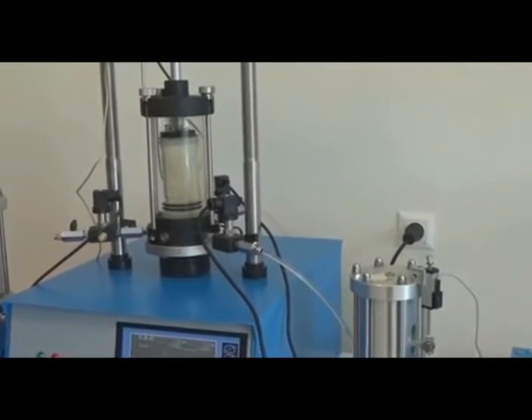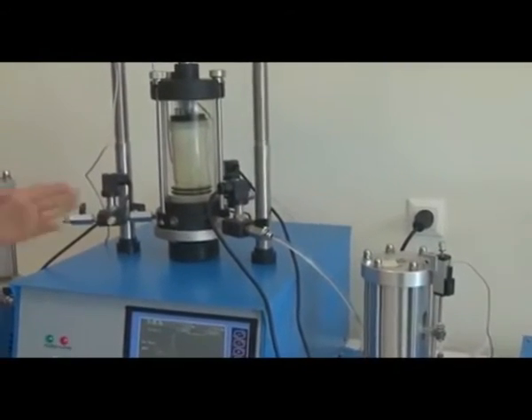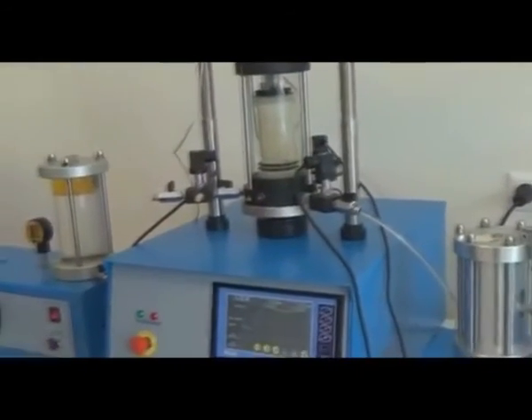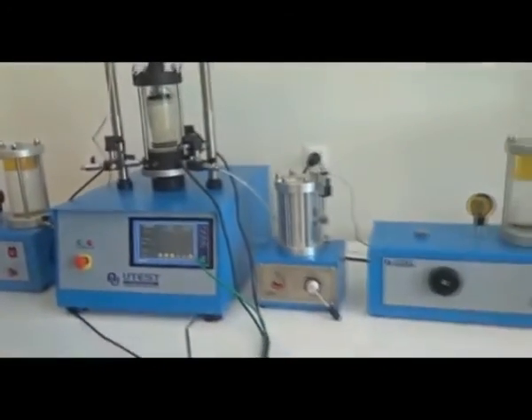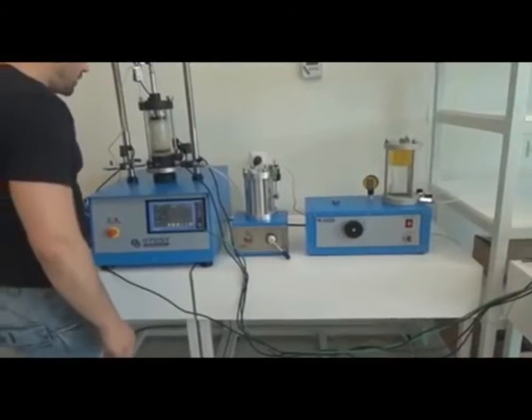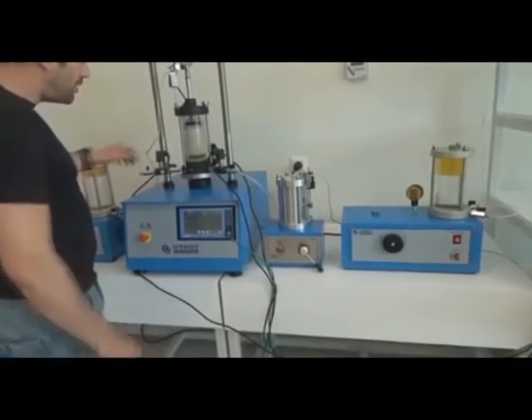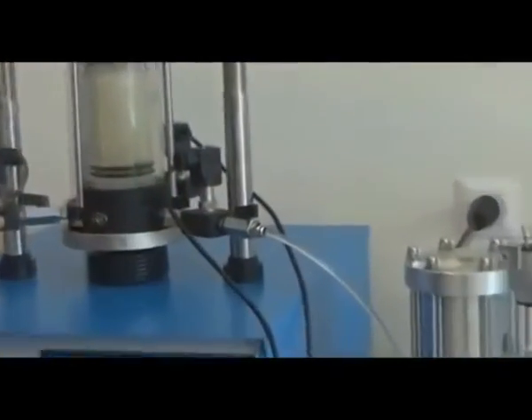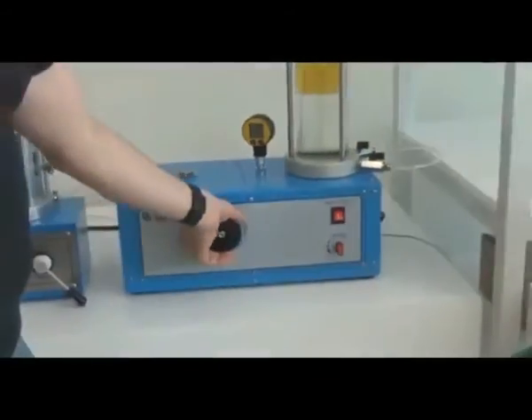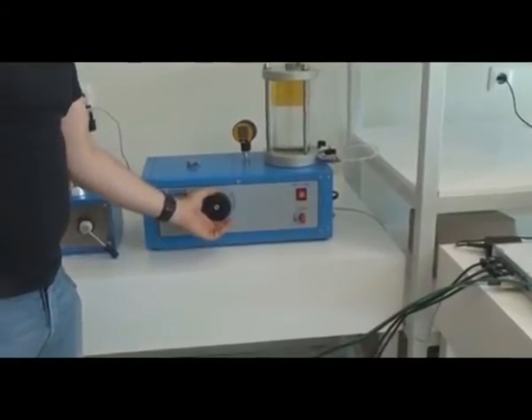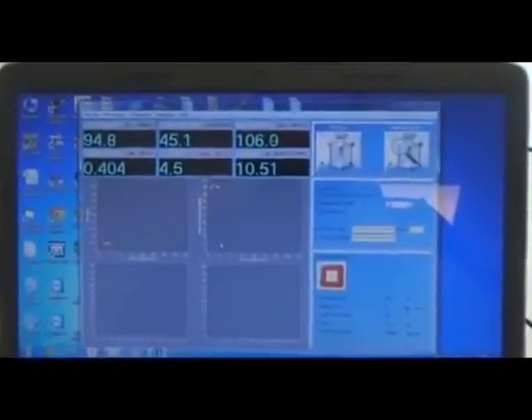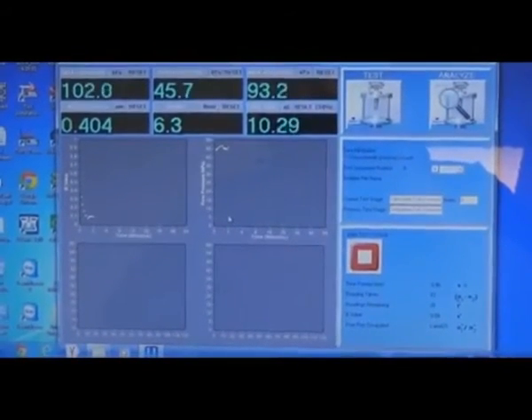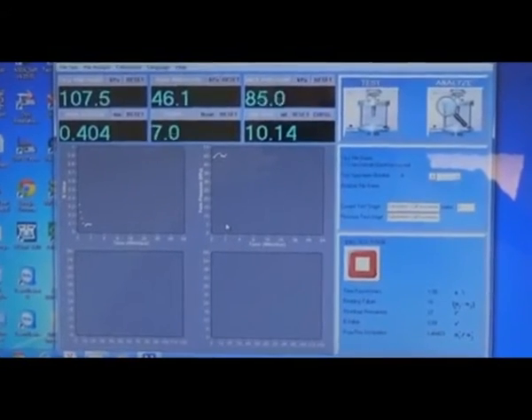And now, since we have 10 kilopascals of pressure difference between cell pressure and back pressure, we are going to increase the back pressure to 90 kilopascals. In order to do that, we are going to close again the inner valve on the back pressure unit and increase the pressure using this knob. As you can see on the test screen, it has nearly reached 90. Yes, it's now around 90 kilopascals.